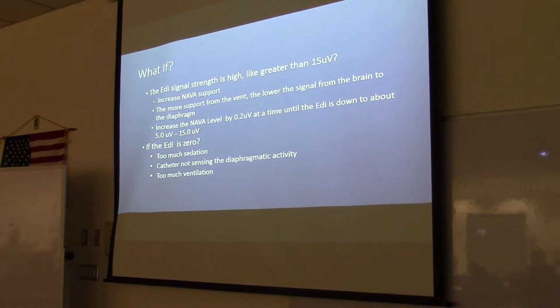So increase the Nava level by 0.2 microvolts at a time until you get your EDI signal down between 5 and 15. So we want the signal to be between 5 and 15.